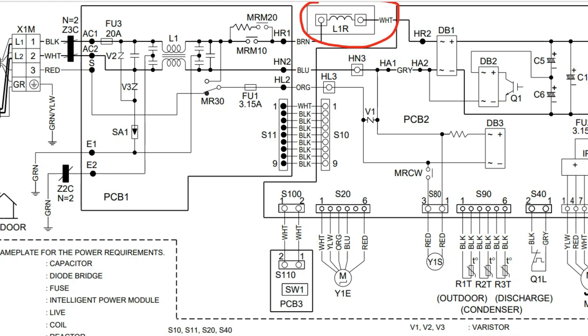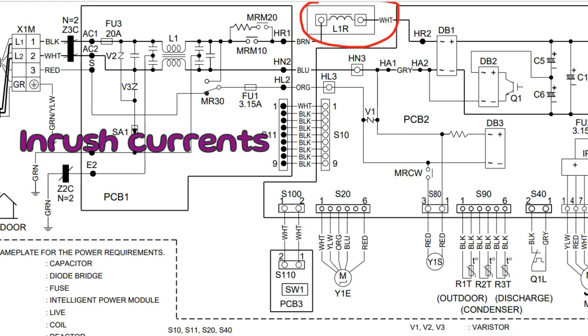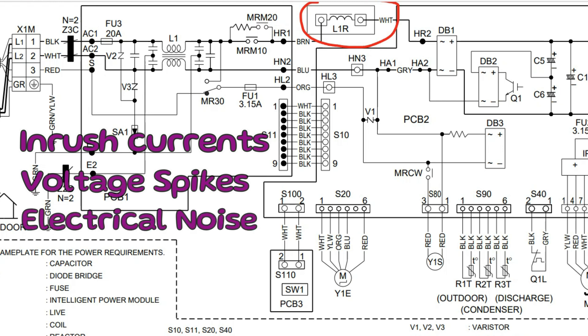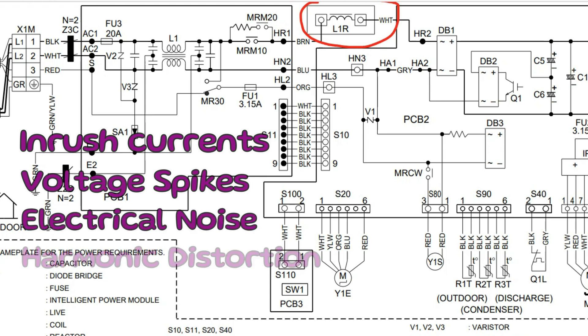The purpose of a reactor is just another layer of filtering. It filters out inrush current — so when a motor first starts up and pulls higher current, it kind of flattens that out. It also helps with voltage spikes, reducing electrical noise and disturbance, harmonic distortions, and power factor. It works on a lot of different things to help stabilize that circuit even more.